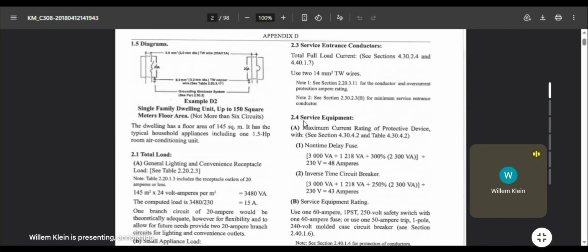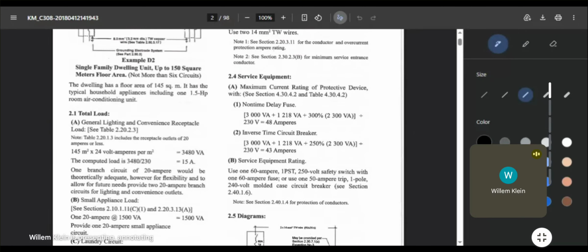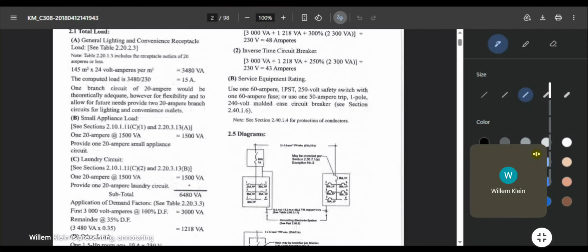And then for the service equipment, when we say service equipment, these are your protection devices. This will depend on your computed full load current for your circuit. So again, how do we compute the full load current? The important parts here: first, you computed your appliance loads and your lighting and convenience outlet loads. Your first 3,000 VA, use 100% of that. And this part is the 35% of the excess. We had an excess of 3,480 right here, so that is included here.